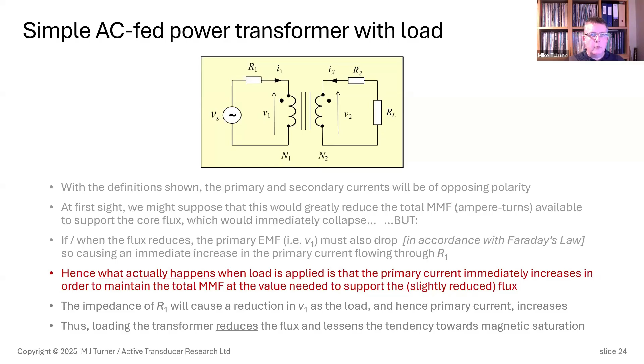So what happens when you apply a load is that the voltage drops very slightly because of the primary winding resistance. The voltage on the primary drops too, and that means the flux in the core drops a little bit. So loading up a voltage-fed power transformer actually decreases the magnetic flux in the core and gives the transformer an easier time from a magnetic perspective. Obviously it heats the windings up, which is why we can't carry on doing it indefinitely, but nevertheless the core is not the problem when it comes to loading up a transformer.